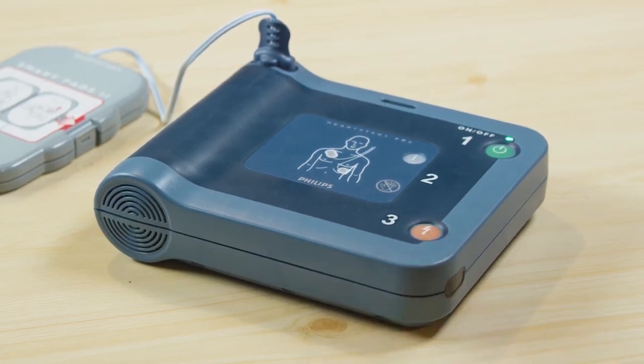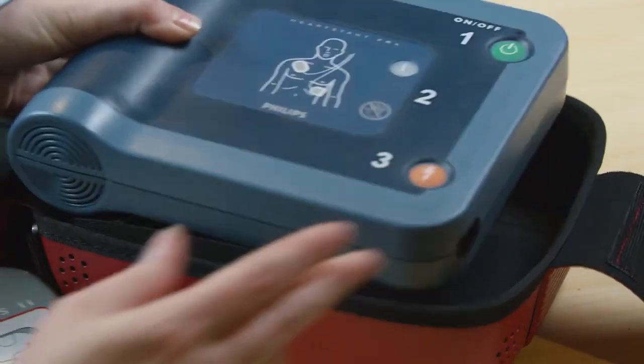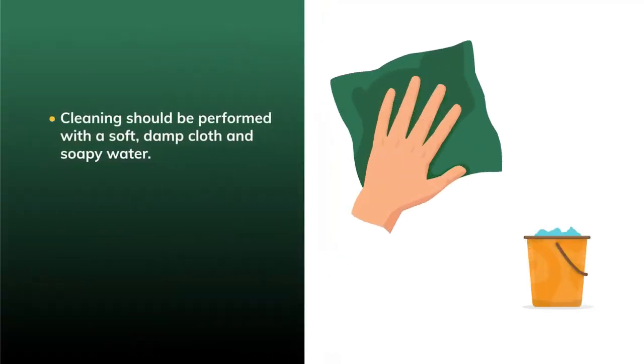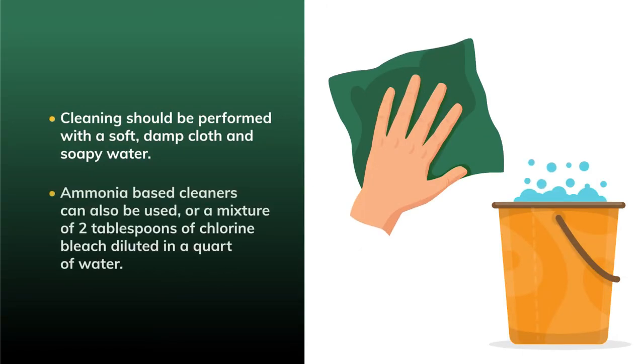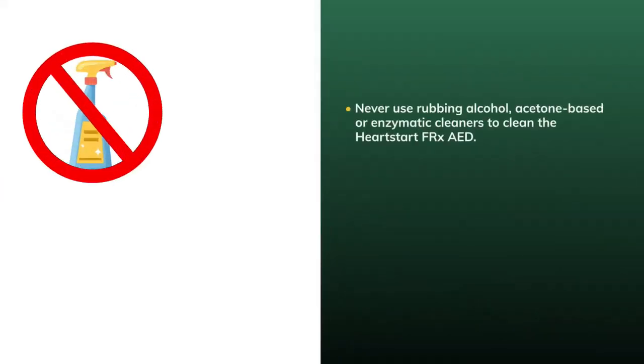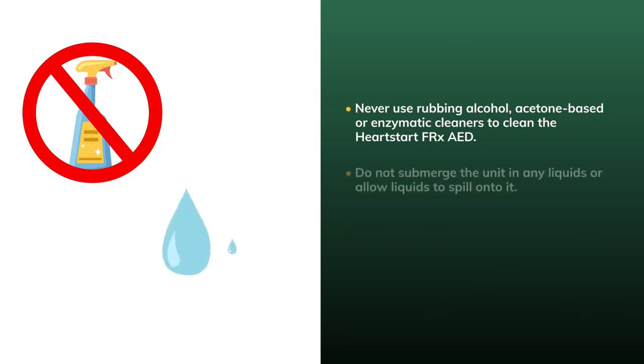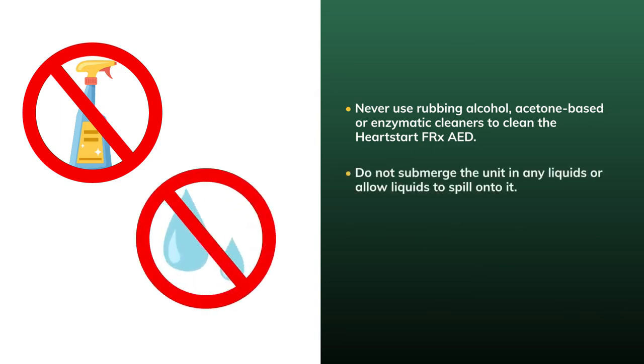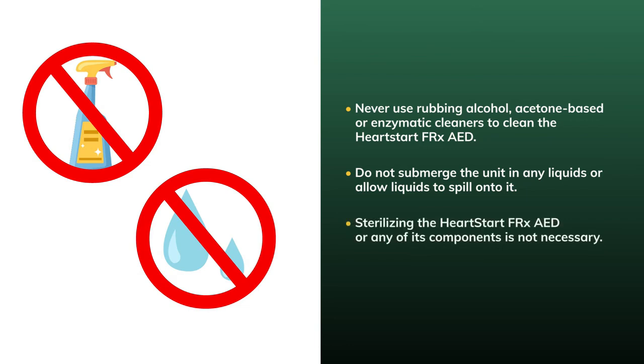After using the HeartStart FRx AED, check the outside of the unit for damage or dirt. Cleaning should be performed with a soft, damp cloth and soapy water. Ammonia-based cleaners can also be used, or a mixture of 2 tablespoons of chlorine bleach diluted in a quart of water. Never use rubbing alcohol, acetone-based, or enzymatic cleaners to clean the HeartStart FRx AED. Do not submerge the unit in any liquids or allow liquids to spill onto it. Sterilizing the HeartStart FRx AED or any of its components is not necessary.